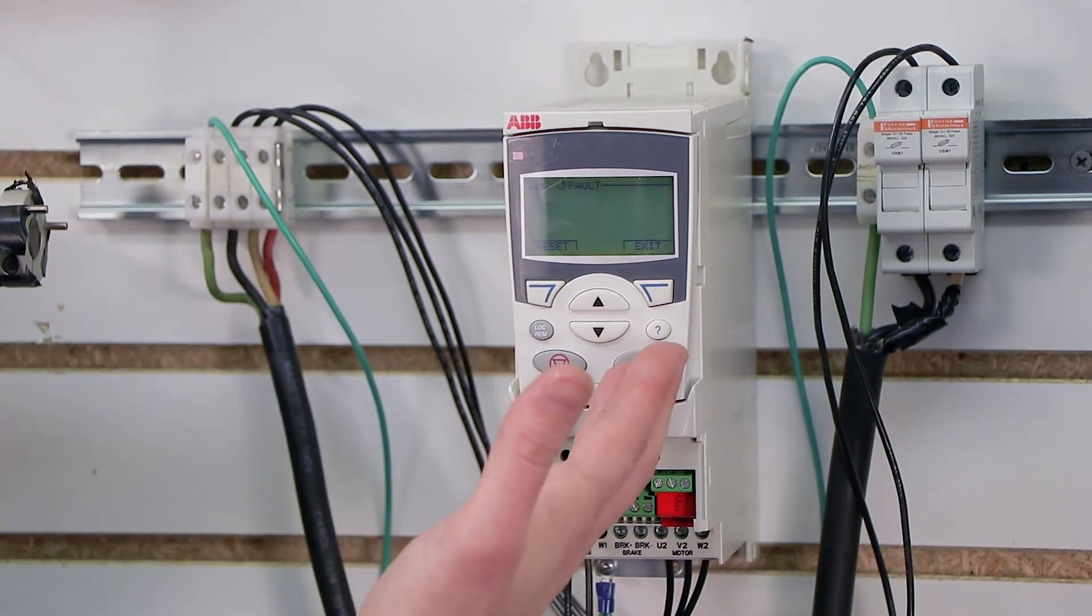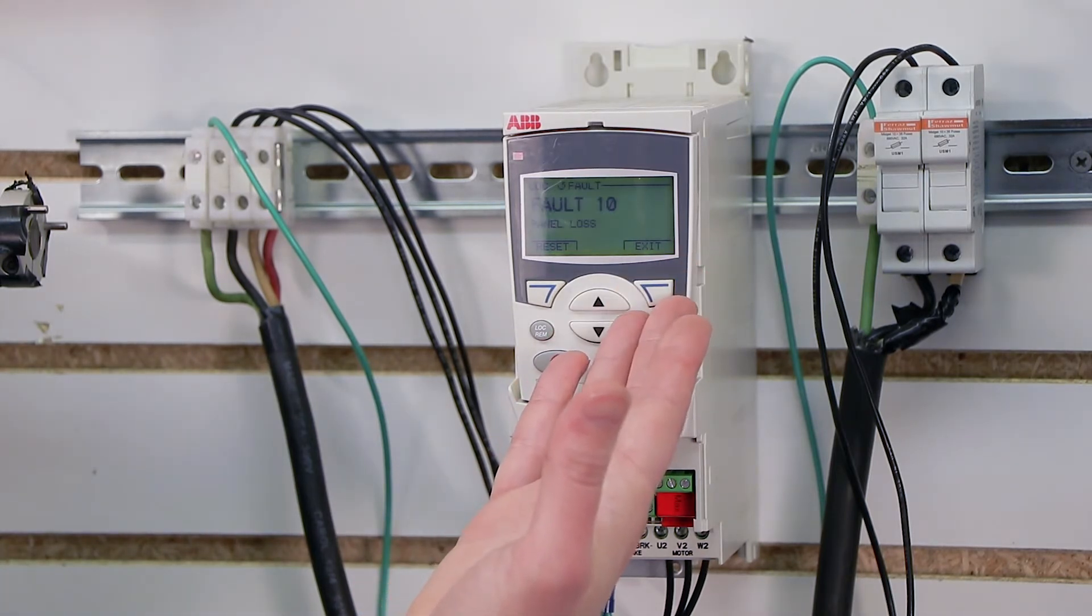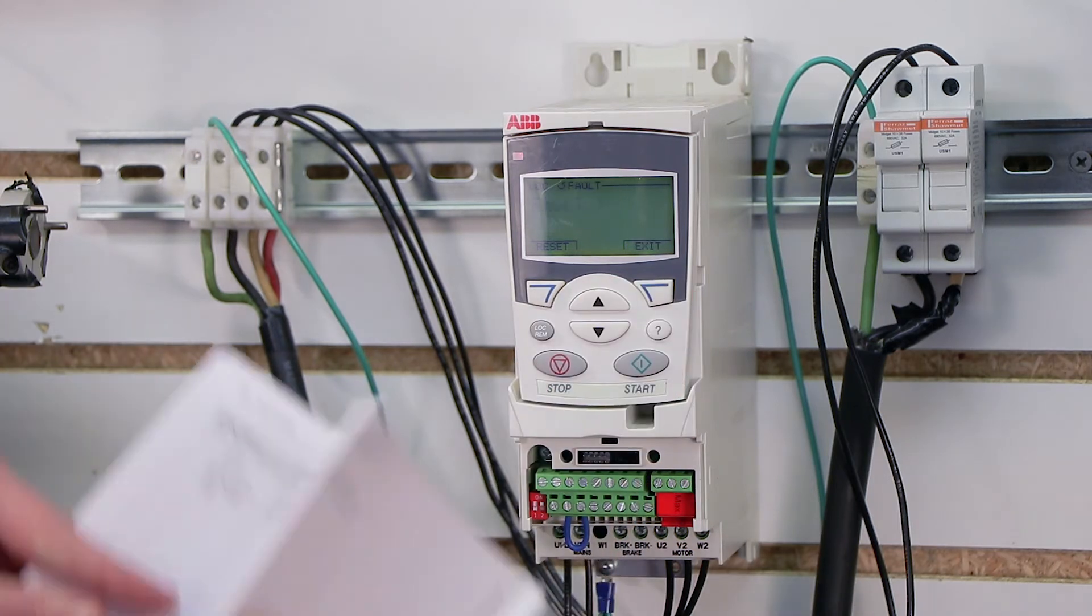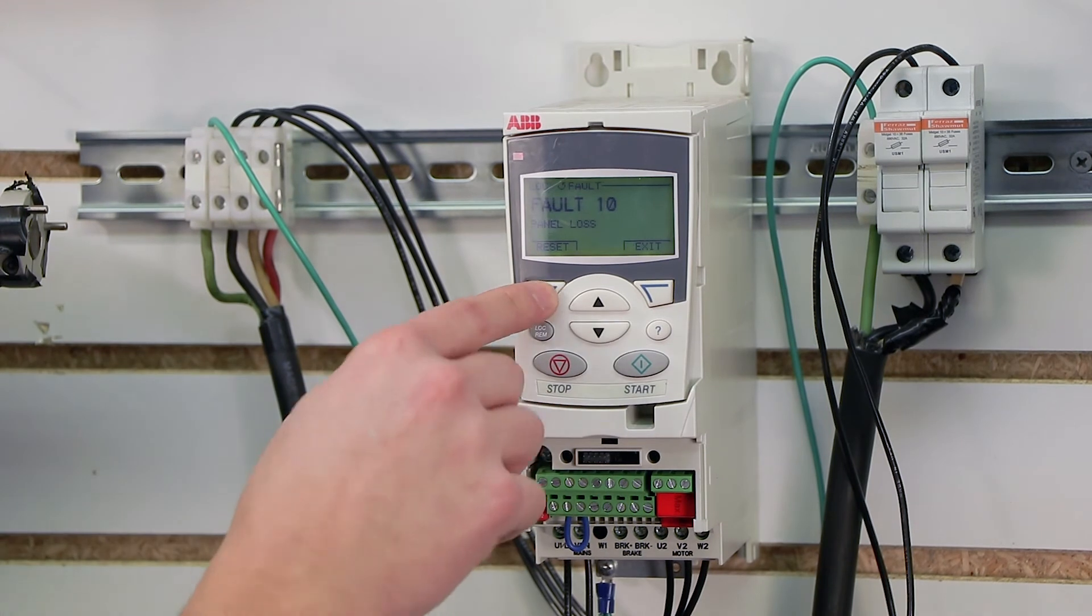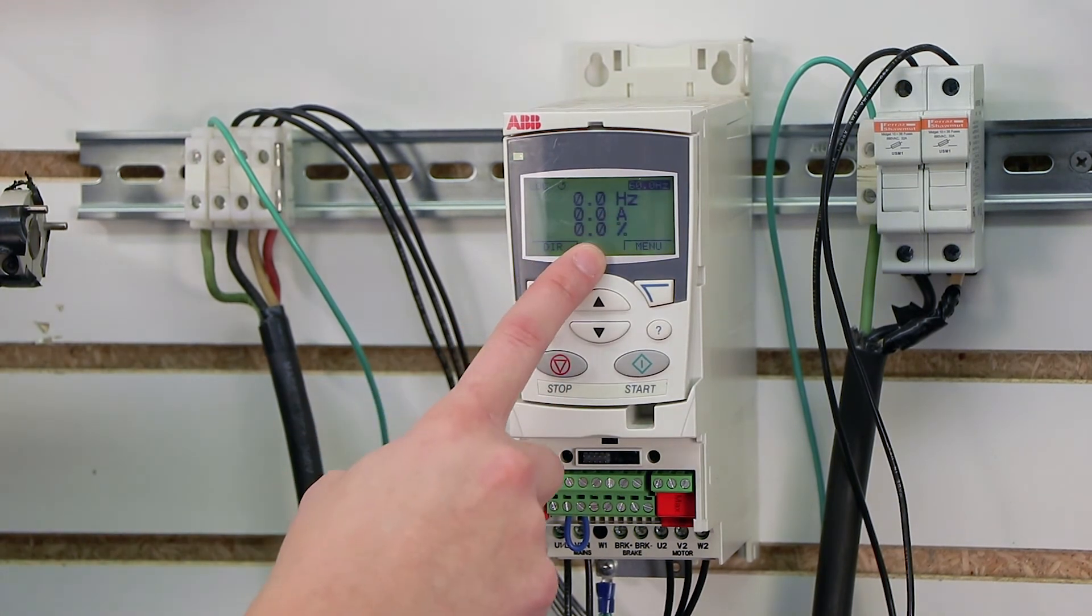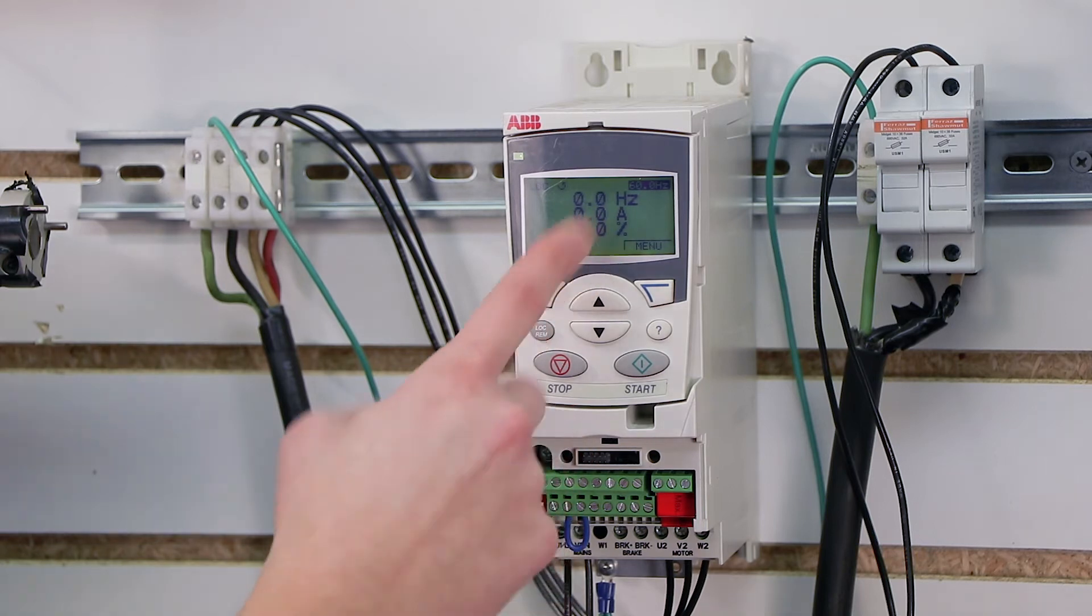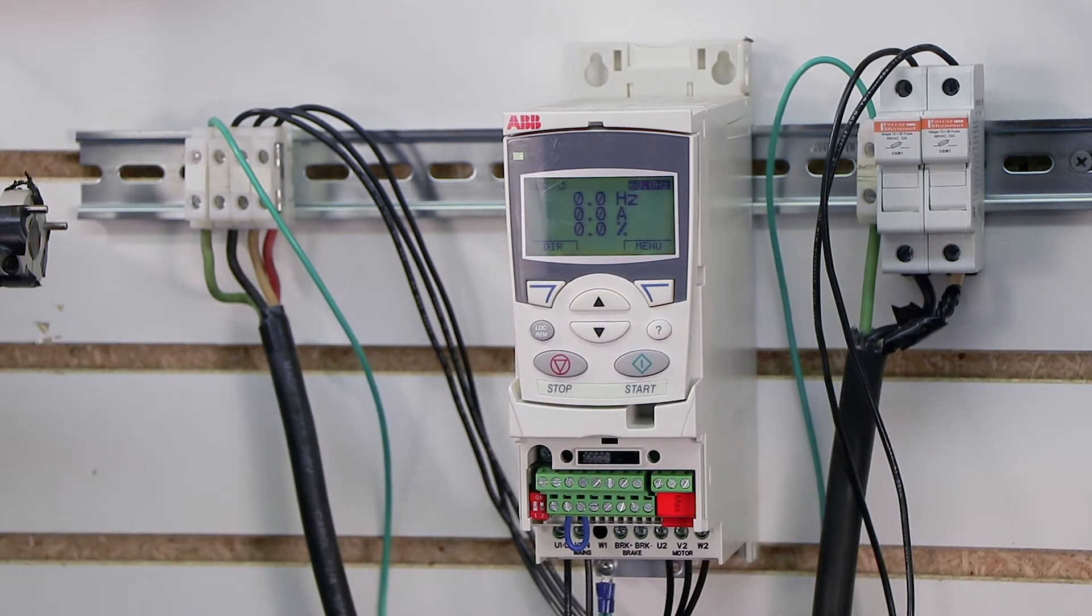Most common issue you get with these drives is a DC bus fault because they're stopping the load too quickly. And again, you can go right through the manual and diagnose that issue. But a lot of times the solution to that is simply to increase the deceleration rate to make it take more time. But that's just one example of going through and tracing a fault.